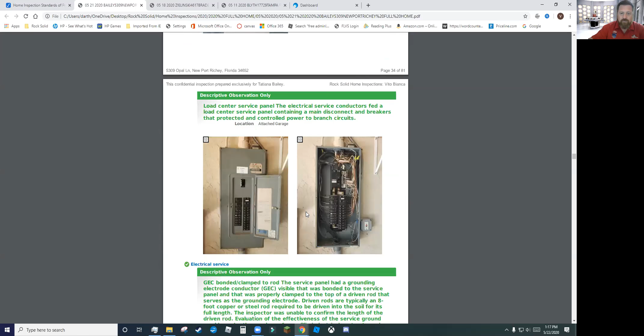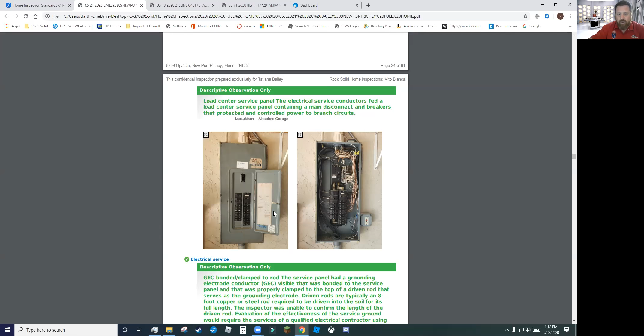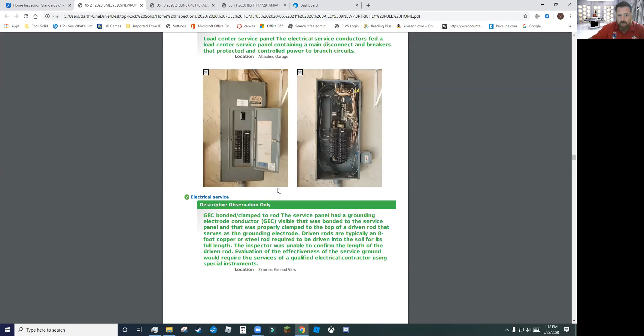We take pictures of the circuit directory. We describe the panel - in this case, a load center service panel, meaning it has a main disconnect and breakers that feed power to branch circuits. That's as deep as I want to get. Of course, I'm looking for grounding and bonding, exposed wires, open knockouts, holes in the metal. I'm making sure wires coming in are either in conduit or clamped with bushings around entry points, and so on. In this case, the panel was really clean, even though a little older, minus the double tap neutrals.